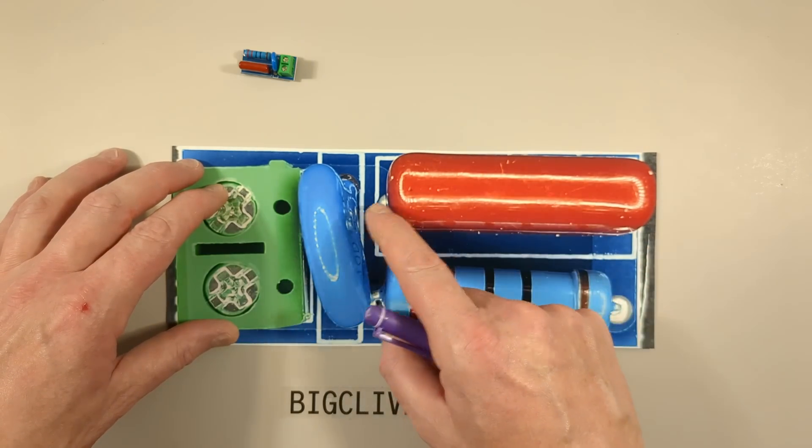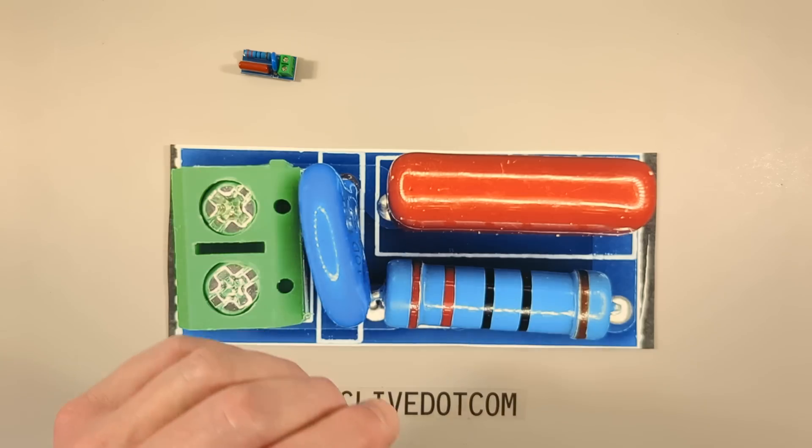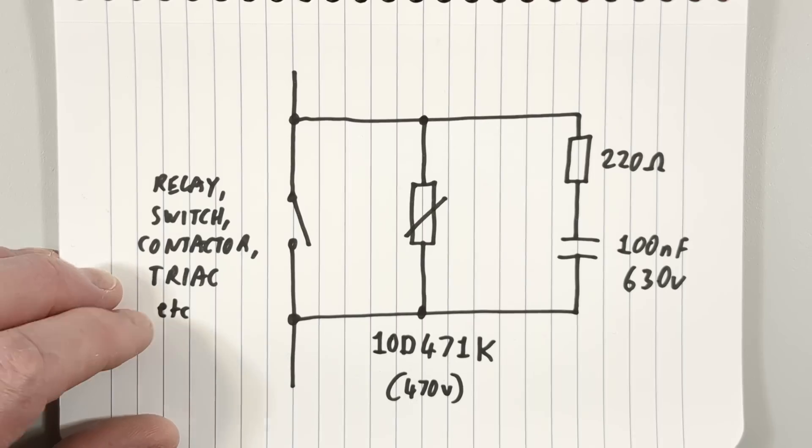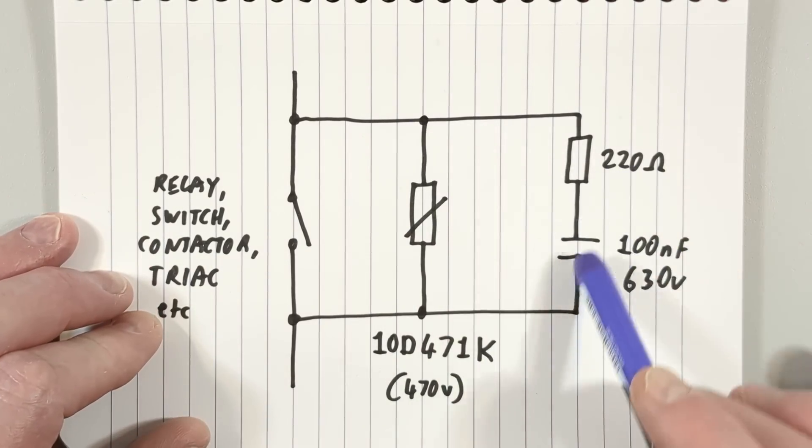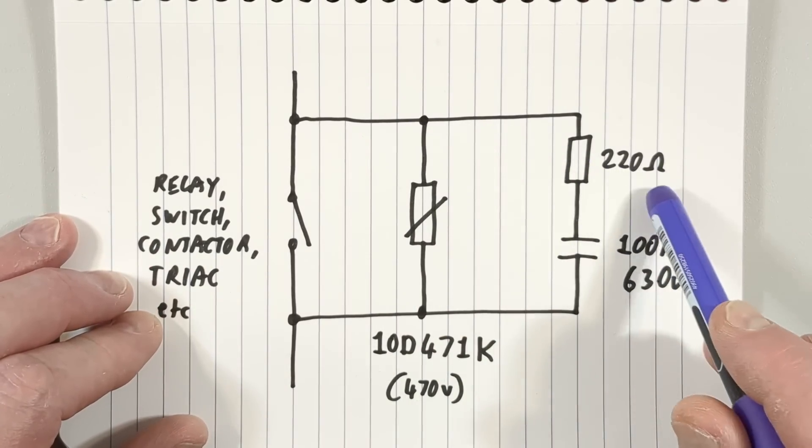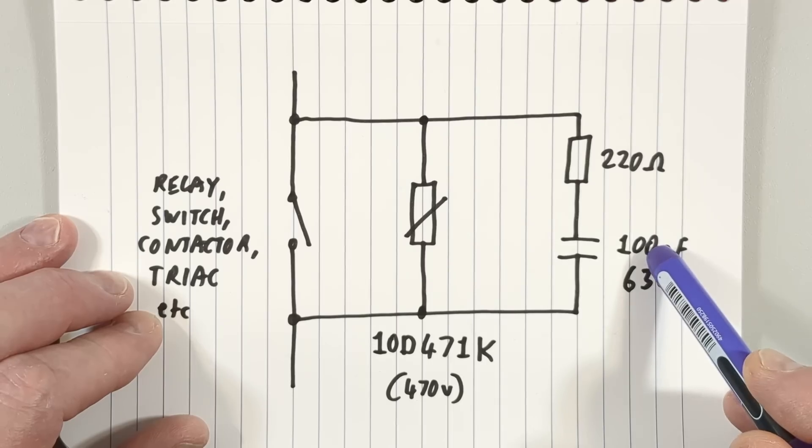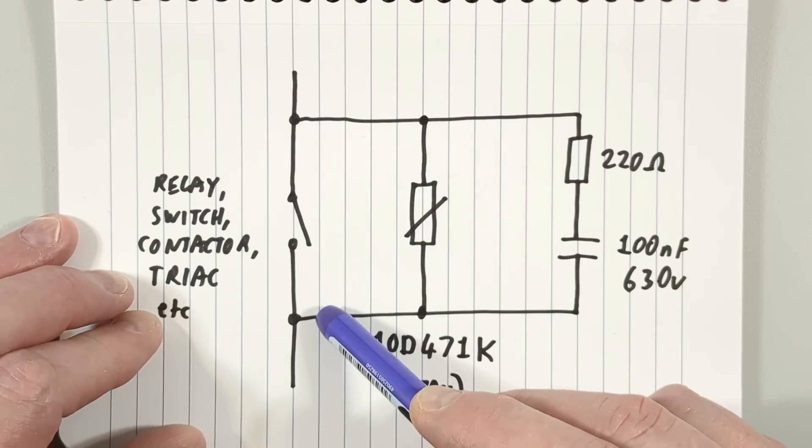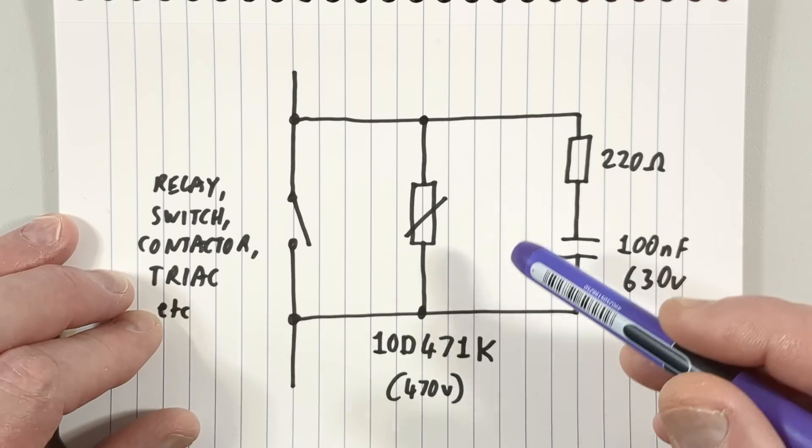Let me show you the schematic of this. The classic snubber network is usually a 100 ohm resistor and a 100 nanofarad capacitor hooked across a relay contact, and it has multiple functions.